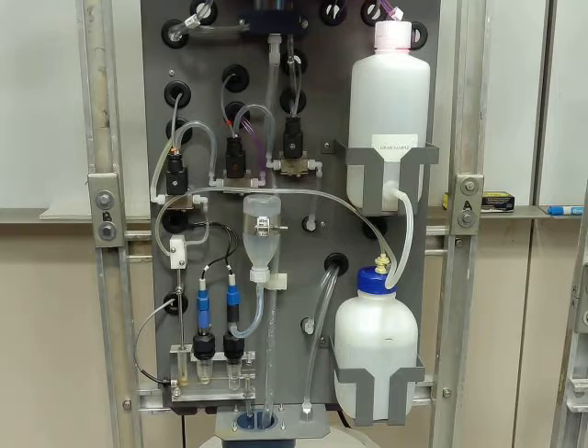All right, so with the reagent buffer again, we're probably going to say it a lot, but replacing that on a monthly basis is definitely the most important thing to keep in mind in terms of maintenance and keeping it running properly. Again, dumping that solution out is critical, not just refilling the bottle. And you can definitely smell the difference between fresh ammonia and unfresh ammonia, as it ages.